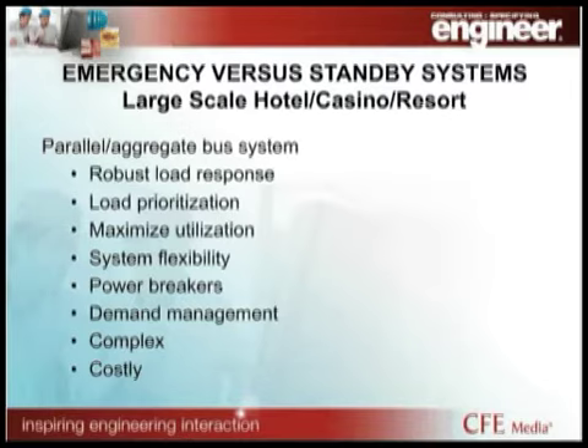And for the 10-second loads, there's multiple ways to set it up, but one of the ways I like to do it, the load bus is active when you're on normal power. You lose normal power, every device but your emergency device opens, and as soon as that first generator attaches to the bus, it takes over the load. And typically it's sized, we're talking engines anywhere from the 1250, 1500 to 2 meg range that we would typically use to create a large-scale load bus. You can also maximize utilization of your engines because you've got real-time demand management, load management within a paralleling arrangement that typically you wouldn't get with a distributed system.